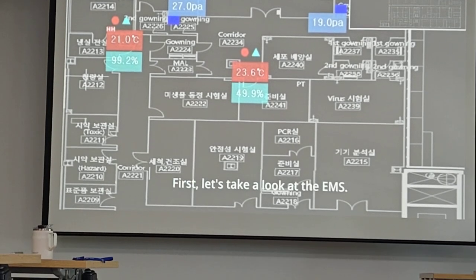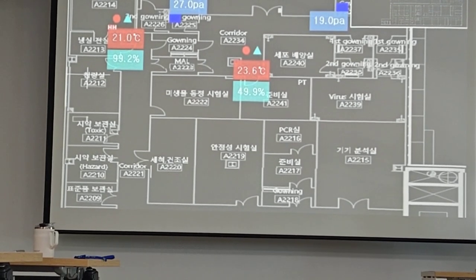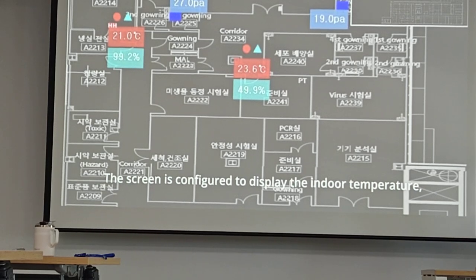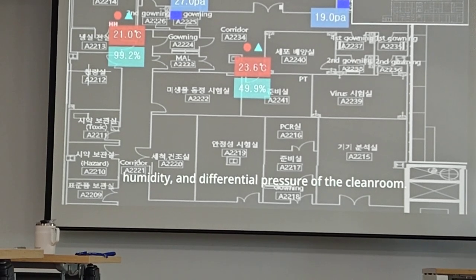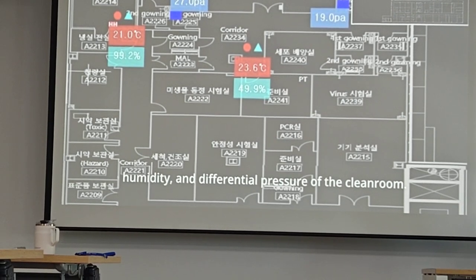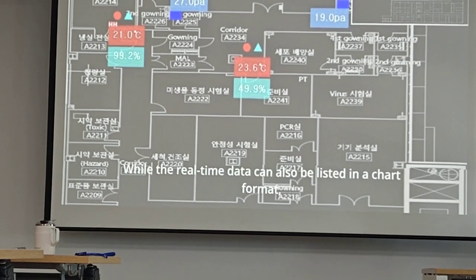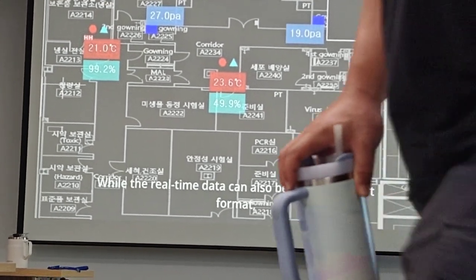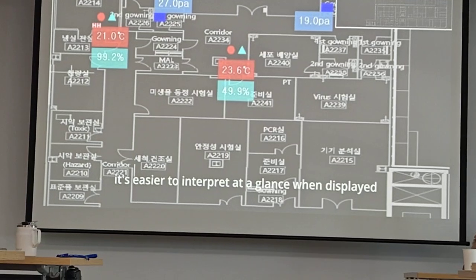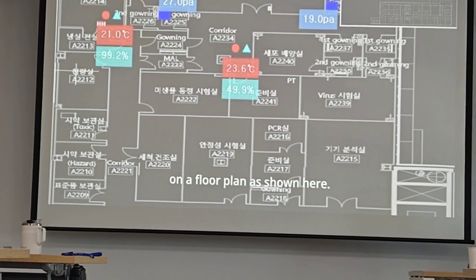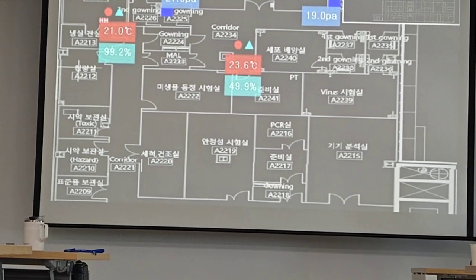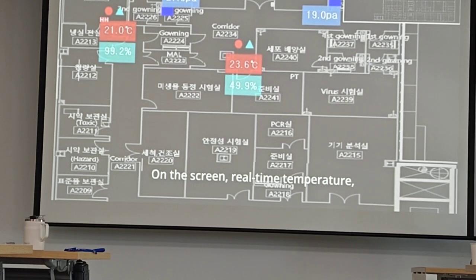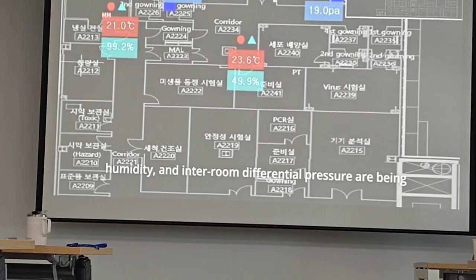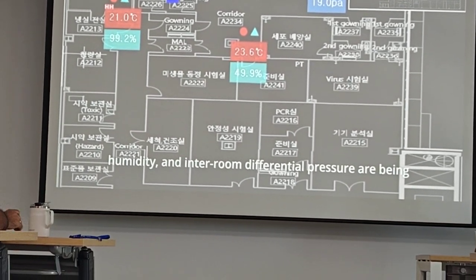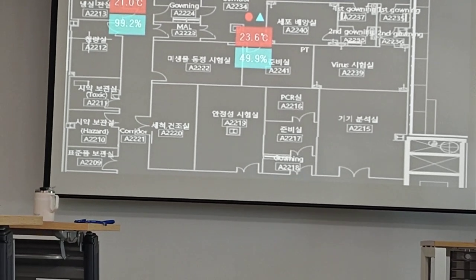First, let's take a look at the EMS. The screen is configured to display the indoor temperature, humidity, and differential pressure of the cleanroom. While the real-time data can also be listed in a chart format, it's easier to interpret at a glance when displayed on a floor plan, as shown here. On the screen, real-time temperature, humidity, and inter-room differential pressure are being monitored and stored.